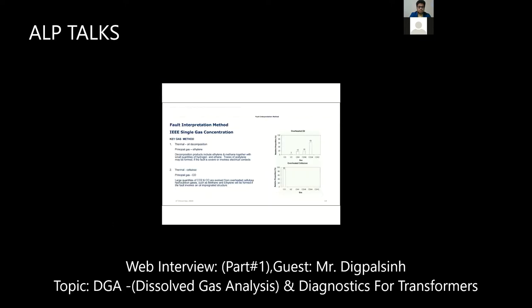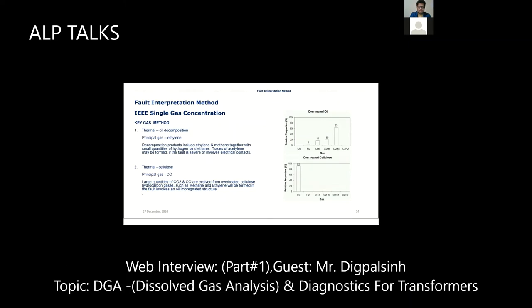Now we will see fault interpretation methods. There are a number of methods for DGA interpretation. I follow IEEE, IEC, CIGRE, and my favorite is Duval, and sometimes Rogers for typical cases. But there are others too: KEMA has developed its own DGA program, ABB has its own DGA program, CBIP has some defined methods, some superseded ones such as Doernenburg, and Siemens also has its own program. Here I am discussing IEEE. So today we will see IEEE, IEC, CIGRE, and Duval.